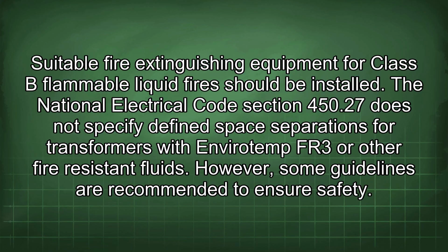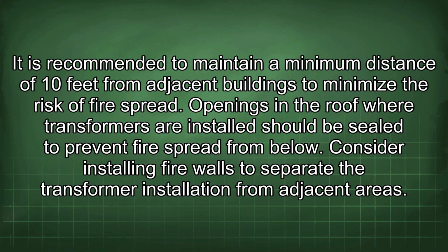The National Electrical Code Section 450.27 does not specify defined space separations for transformers with Envirotemp FR3 or other fire-resistant fluids. However, some guidelines are recommended to ensure safety. It is recommended to maintain a minimum distance of 10 feet from adjacent buildings to minimize the risk of fire spread. Openings in the roof where transformers are installed should be sealed to prevent fire spread from below. Consider installing fire walls to separate the transformer installation from adjacent areas.